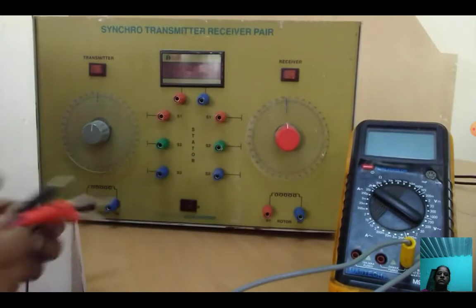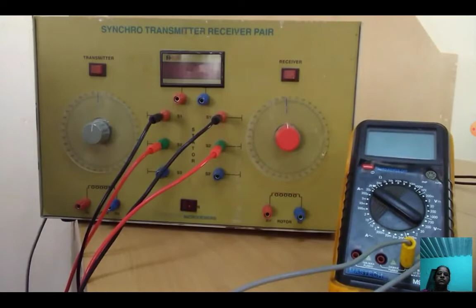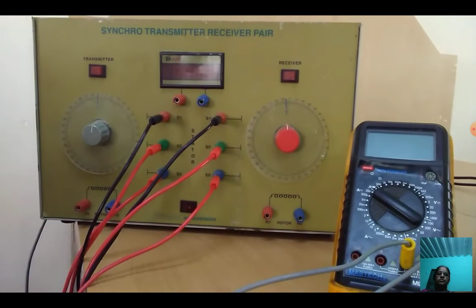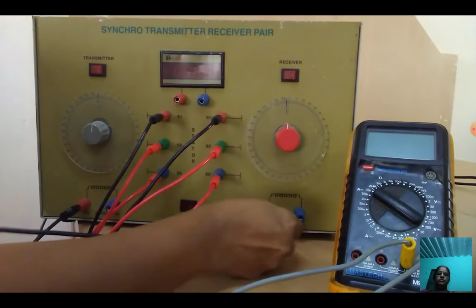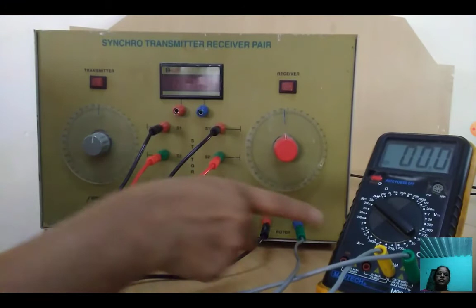Connect S1 to S1 dash, S2 to S2 dash, S3 to S3 dash, and R1 to R1 dash. For R2 we connect the multimeter: R2 dash is connected to the voltage terminal of the multimeter, and the common terminal of the multimeter goes to R1 dash and R2, with the multimeter set to AC mode only.